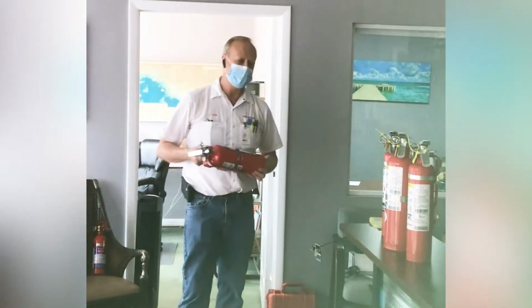You need to have this in there. We tell every yacht owner that we go on their boat, and most of the time they replace it because they understand. And when it comes to insurance, say they have a fire and they discharge the ABC dry chem, the insurance will pay your claim for whatever damage was done. Well, 6 months down the road, your electronic equipment is faltering or going out, dying because that infiltrated it and just corroded it. So that's a really good selling point. Then your insurance isn't gonna pay you anything after the first claim, right? So you're stuck paying whatever damage is done. So that's why you really use the clean agent when you can. You will absolutely have ghost problems.